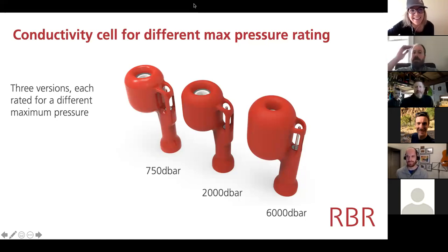Right. And I know that they also did some work with Turner Designs on coating the fluorometers, but I think they had some problems with the optical transparency of it. Although by eye it is clear, clearly when you're working with a fluorometer, it's not. Right. I think that there are a number of techniques: chemical, mechanical, wipers and plungers, that kind of chimney sweep arrangement. There's also using UV to do anti-fouling. But the problem with UV that nobody is going to overcome is that UV LEDs are too inefficient. For every watt of electrical power you put in, you get less than a milliwatt of photons out. And so they're right at the edge of the spectrum for solid state light emitting diodes at the moment.